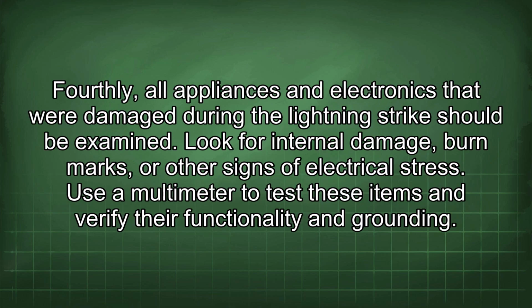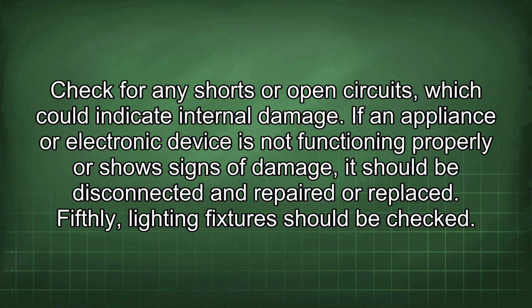Fourthly, all appliances and electronics that were damaged during the lightning strike should be examined. Look for internal damage, burn marks, or other signs of electrical stress. Use a multimeter to test these items and verify their functionality and grounding. Check for any shorts or open circuits, which could indicate internal damage. If an appliance or electronic device is not functioning properly or shows signs of damage, it should be disconnected and repaired or replaced.